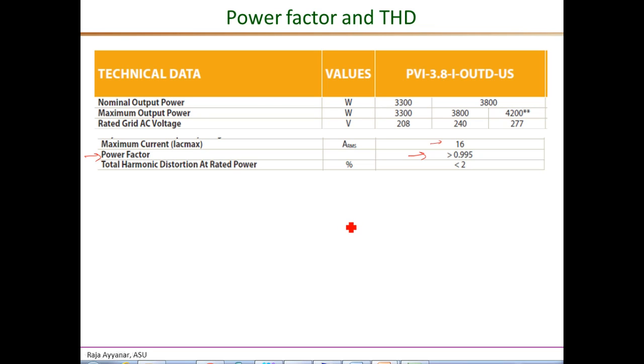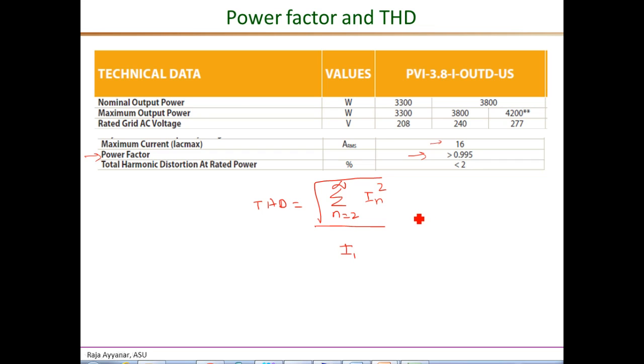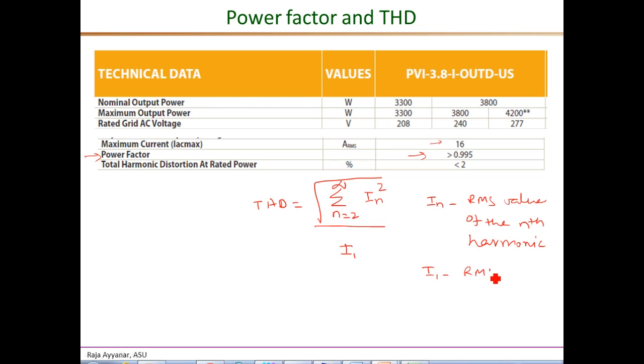THD is the ratio of the harmonic content in the current waveform to its fundamental component. A commonly used definition is: THD = sqrt(sum from n=2 to infinity of In²) divided by I1, where n is the order of the harmonic, In is the RMS value of the nth harmonic component in the line current, and I1 is the RMS value of the fundamental component. So it is the ratio of the total harmonic content to the fundamental component in the line current.